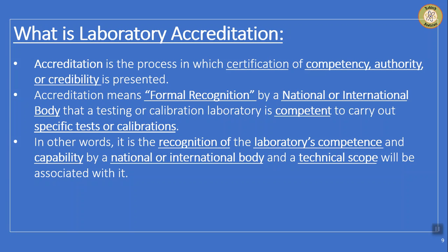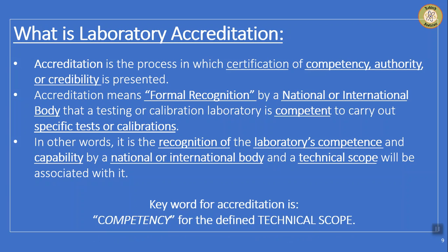So that technical scope will be in details. It will describe the complete list of tests or calibrations, their ranges, their applicable standard methods, and for calibration also CMC, that is calibration measurement capability. So that is also part of the certificate. So you can see the key word for accreditation is competency for the defined technical scope, which is competency term is included in the title of the standard itself. So it is all basically aimed to the competency of the laboratory.